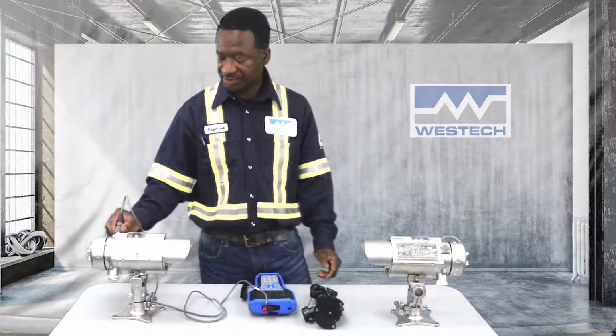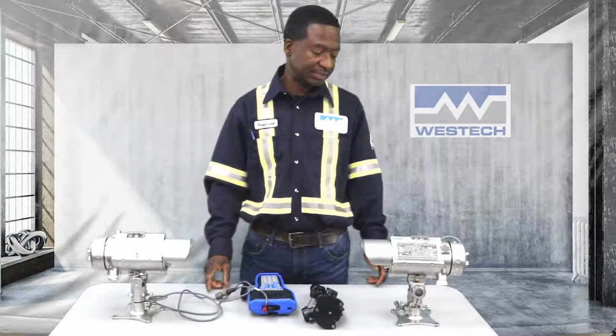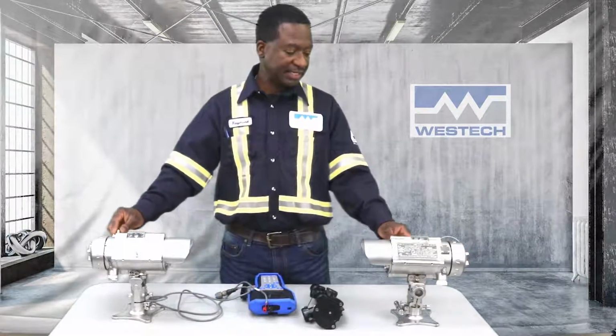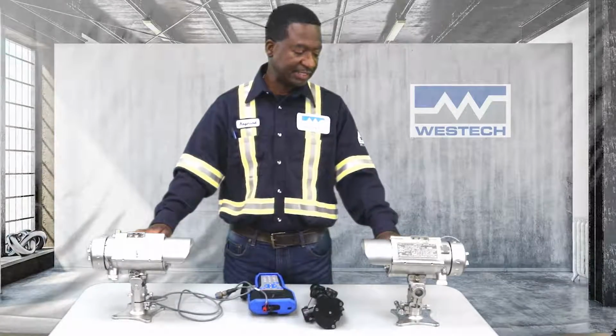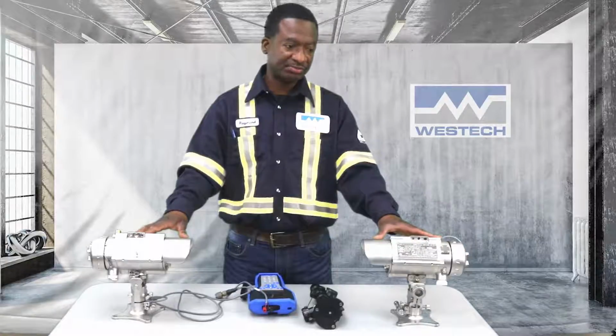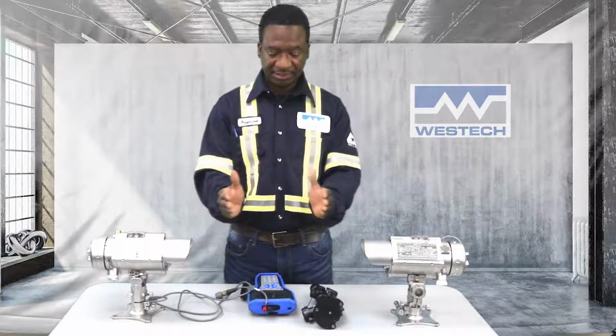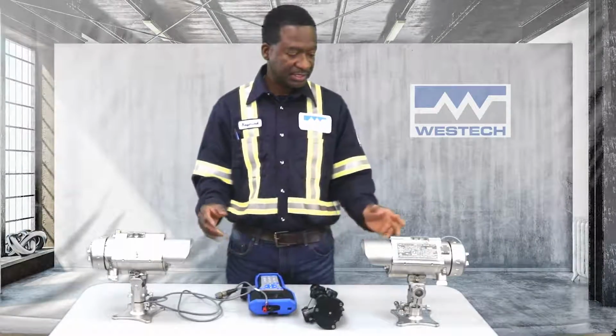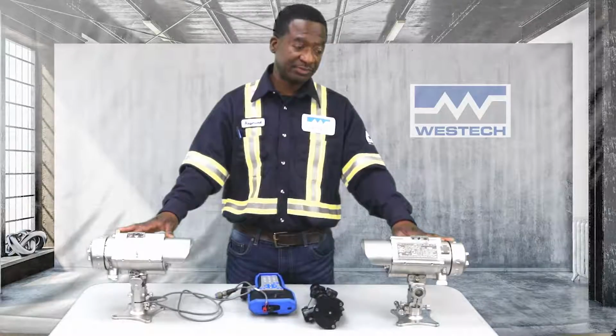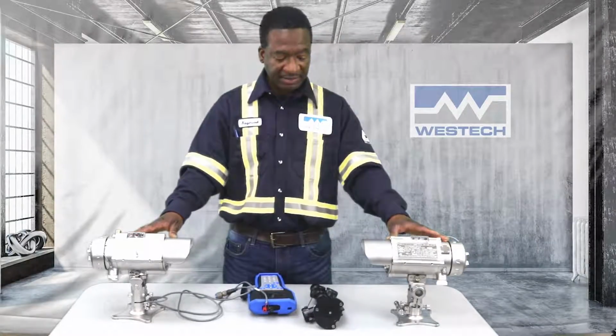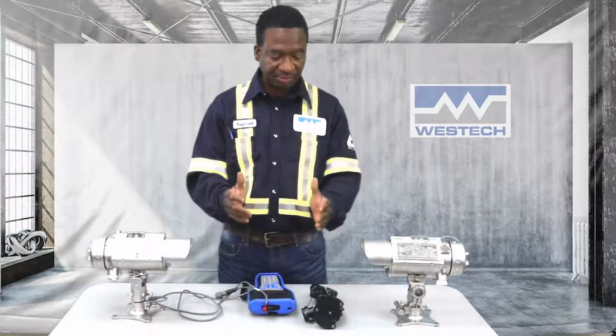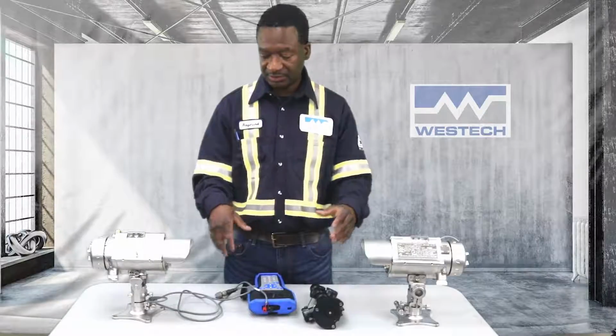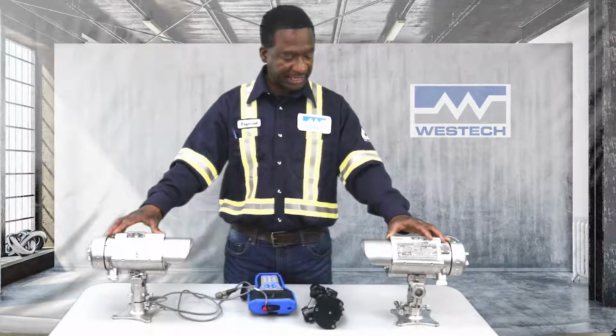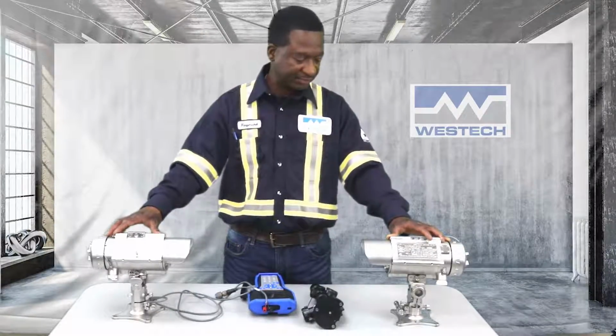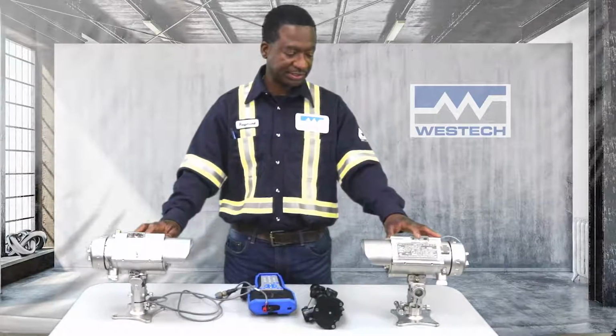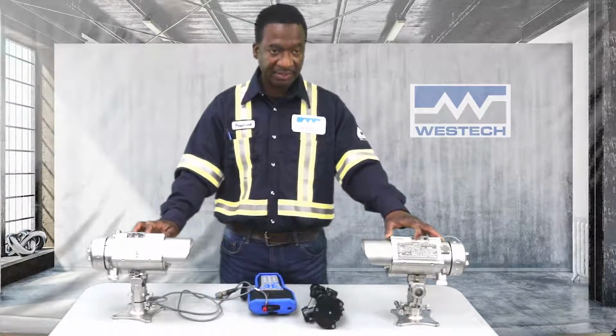Once a zero calibration is done, the unit is pretty much ready for detecting gases. For the LEL system, the unit of measure is the LEL meter, whereby the gas concentration is multiplied by the distance, that is the width of the cloud in that sense. And the unit of measure for the H2S system is the PPM meter. Same concept, whereby it's a product of the concentration multiplied by the width of the gas cloud to get a reading. The scale of the LEL system is 0 to 5 LEL meter, and the scale of the H2S system is 0 to 500 PPM meters.